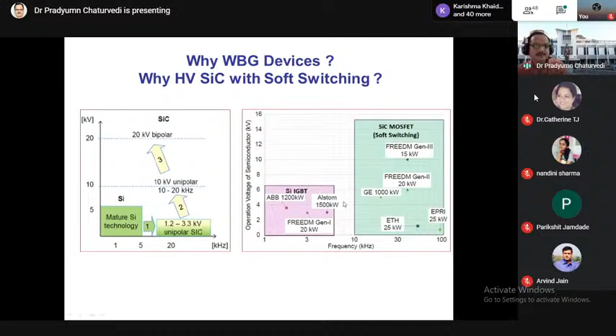Now around 20 kV bipolar silicon carbide devices are available, which can work at around 10 to 15 kilohertz. If you try to reduce the kilovolt rating, then you have to go up to several hundreds of kilohertz switching frequency, because SiC and GaN devices have very low on-state resistance and very low turn-on and turn-off losses, so switching losses are much reduced. Several companies are already manufacturing this type of SiC and GaN based SST for different ratings.